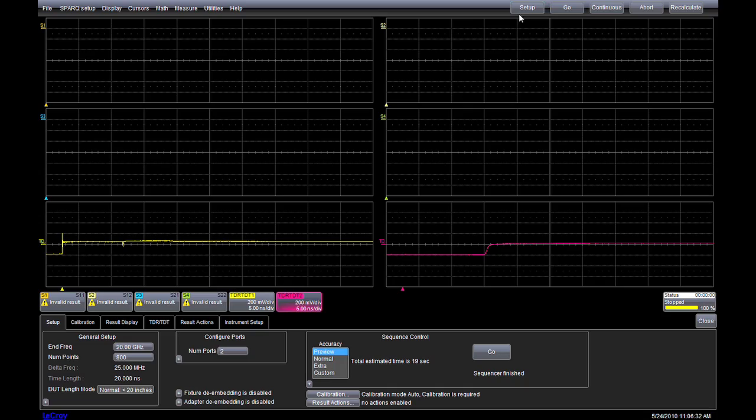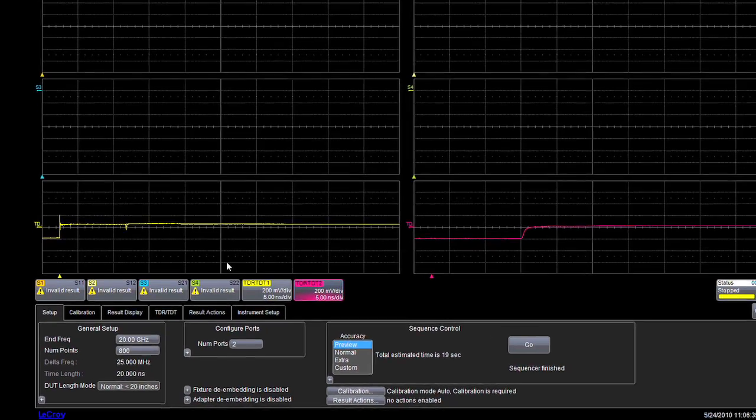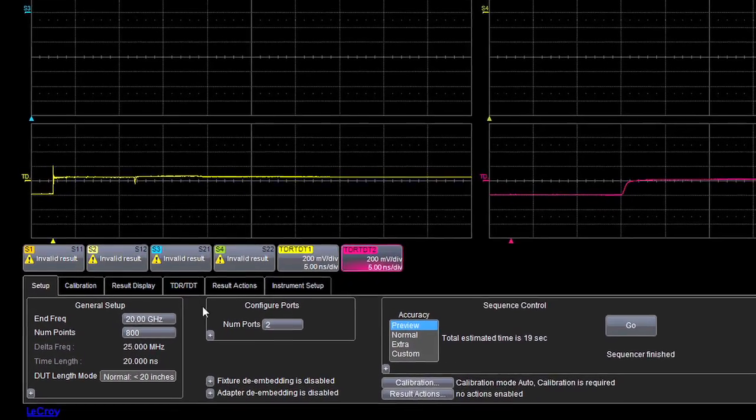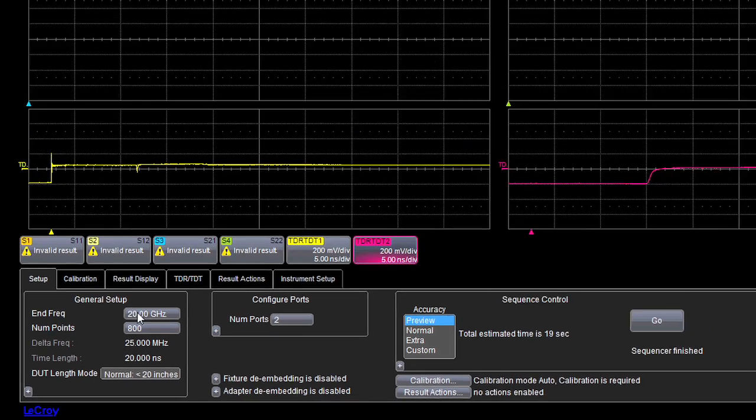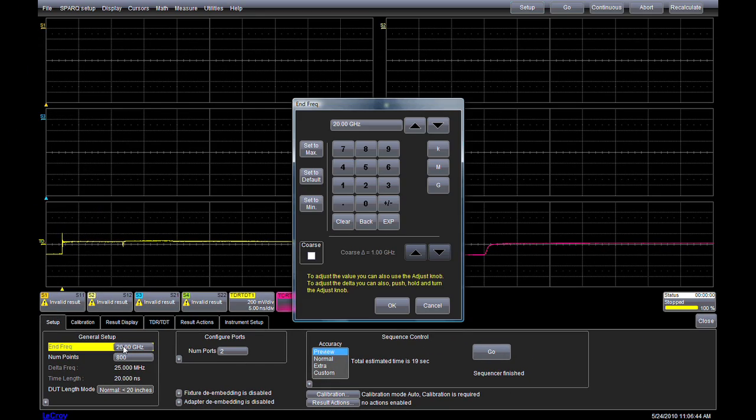I'll click on Setup. Here's where almost all of the settings for S-parameter and time-domain measurements are configured. Currently, we are set up to make a 2-port, 800-point measurement with an end frequency of 20 GHz. Let's change it to 40.